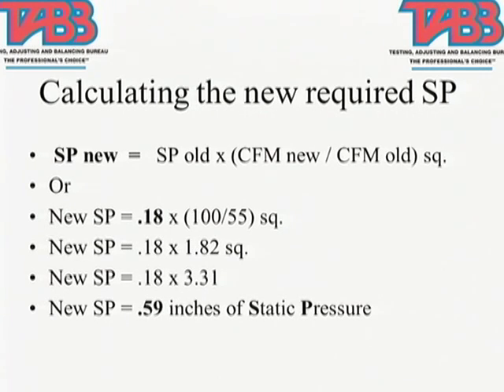So what we started with was 0.18 inches of static pressure in a duct. The commissioning agent came along and said, that's reading too low. What I need you to do is increase the static pressure in that duct up to 0.59 inches. And when you look at it in energy terms, it's craziness. It's crazy to ask someone to do that to the system, because the energy cost is out of control.